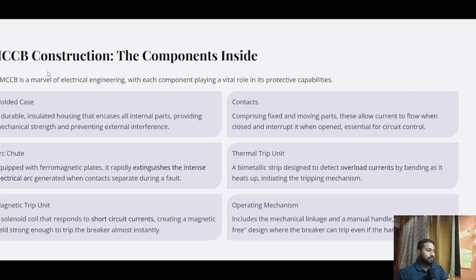Then here is the construction of the components of MCCB. An MCCB is a marvel of electrical engineering, with each component playing a vital role in its protective capabilities. First is molded case. It's a durable insulated housing that encases all internal parts, providing mechanical strength and preventing external interference. Then it has arc chute equipped with ferromagnetic plates. It rapidly extinguishes the intense electrical arc generated when contacts separate during the fault. Then it has magnetic trip unit. It's a solenoid coil that responds to short circuit currents, creating a magnetic field strong enough to trip the breaker almost instantly. Then its contacts comprising fixed and moving parts.